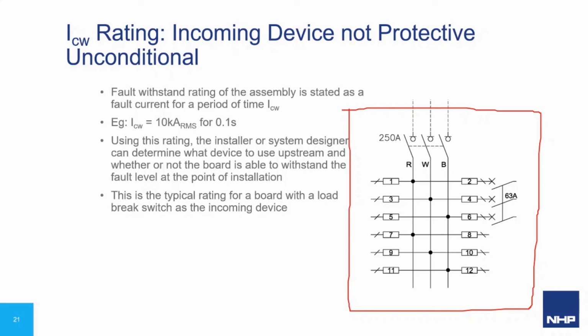This is typical for a board with a load break switch as the incoming device. We cannot use cascade from upstream breakers as it is not stated, although we can use cascade between breakers internal to the board. After that, the breaker can be relied on to protect the conductors and downstream parts like circuit breakers or contactors.